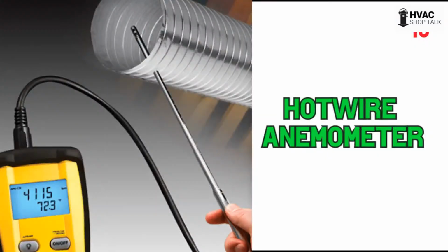But if you would have come at a different angle - keep in mind, you're going across the entire diameter. You're not going to come in there and go across the middle, then through the top section and the bottom section. You're going to go all the way across at angles, up and down, so you can get an average. These machines - I don't know if it's this Field Piece here, I think it might be the Field Piece STA2 or SAT2 or something - you can measure out a few runs and then calculate, which is really nice.